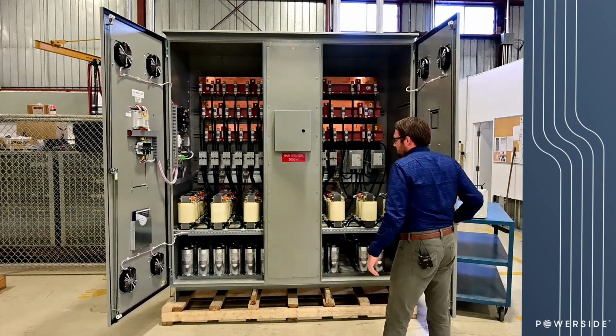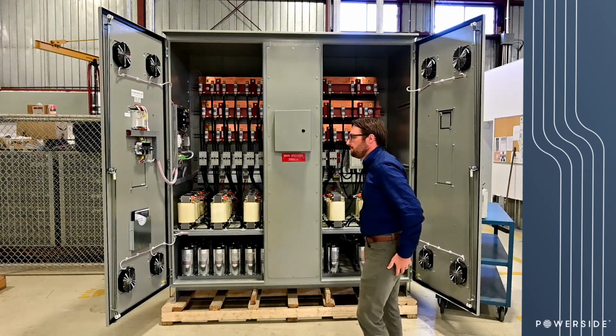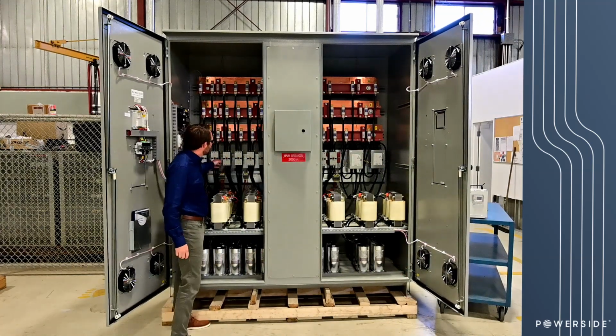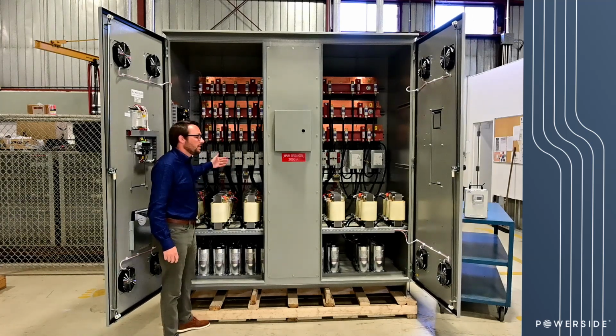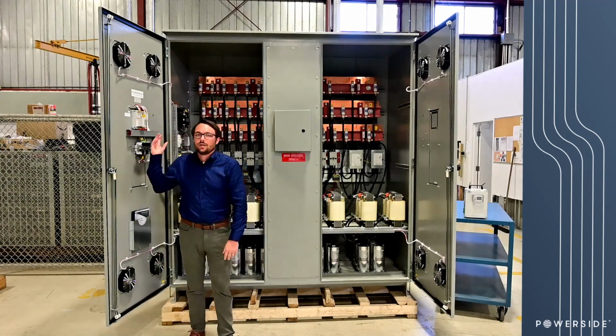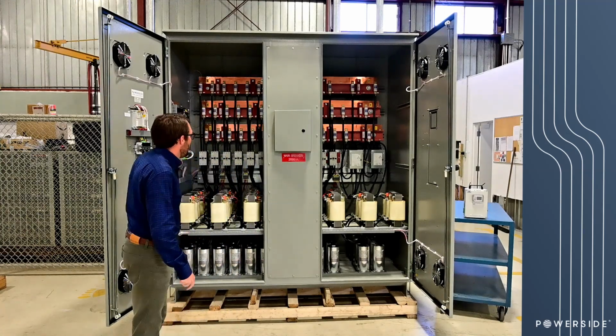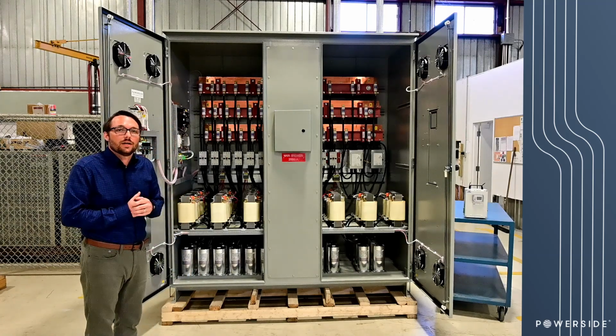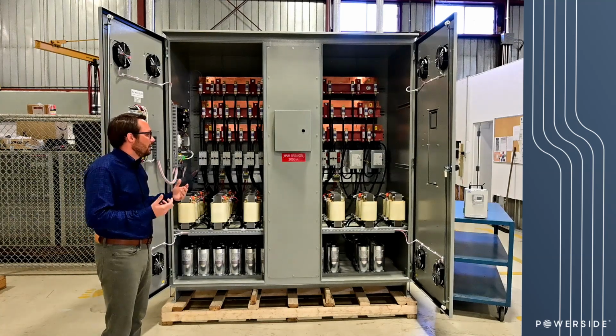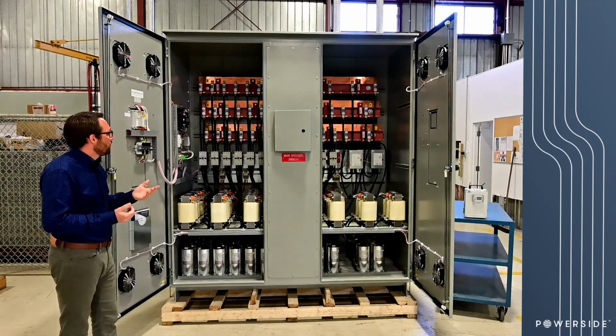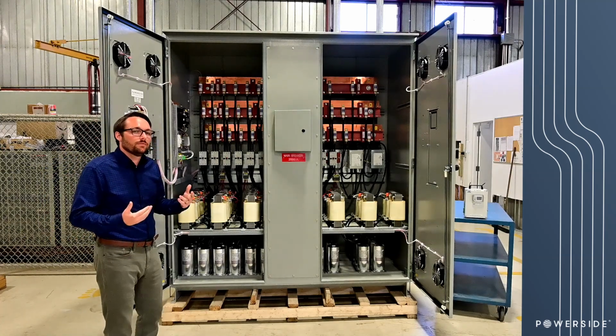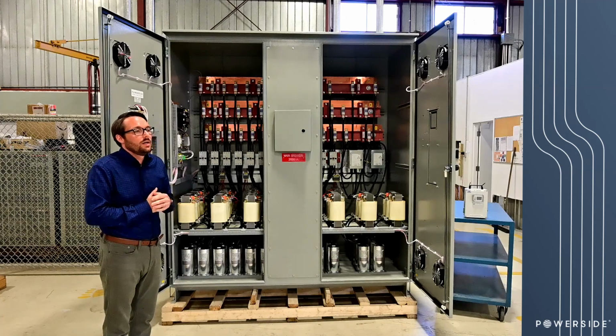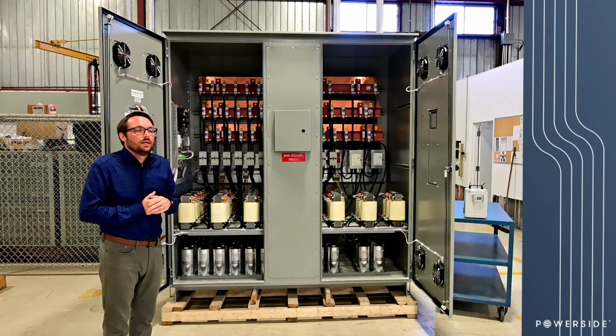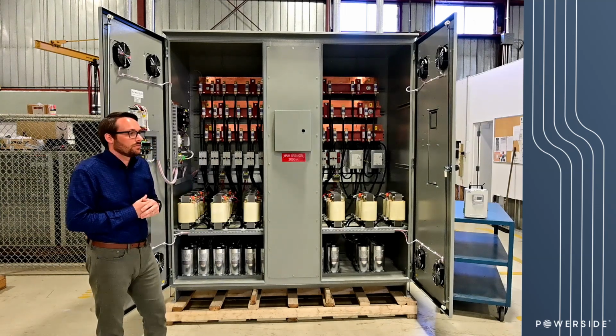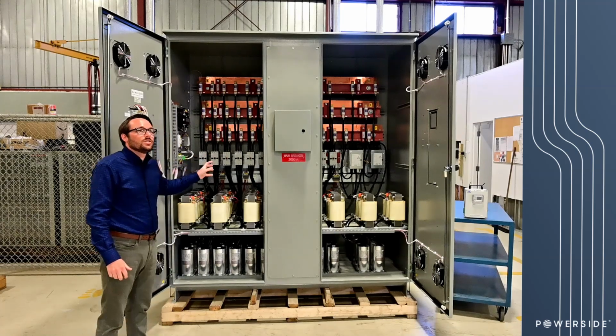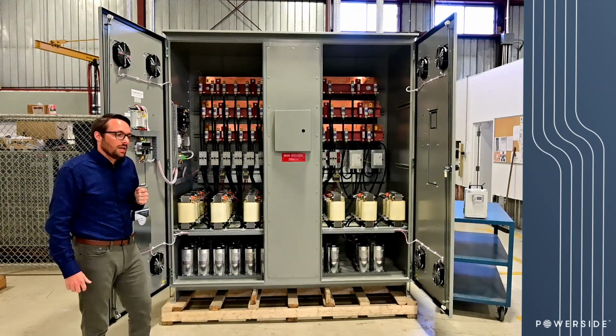So the traditional way to do automatic power factor correction is to use what we call contactor switches. These are contactors, they open and they close based on the control algorithm in the power factor relay. And this works great for loads that do not change extremely frequently and you want to maintain a high power factor. However, when you have loads that cycle fairly quickly, for instance, like we're seeing in this application, or let's say in an application like welding, where you have a very high amount of current for a very short duration, these contactors are not designed to switch on and off that quickly. And there's several reasons for that.